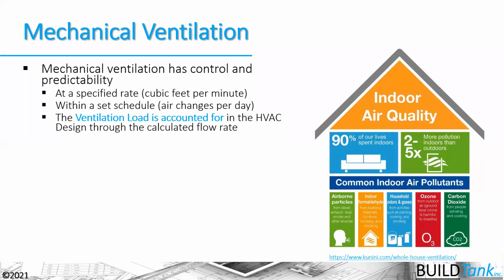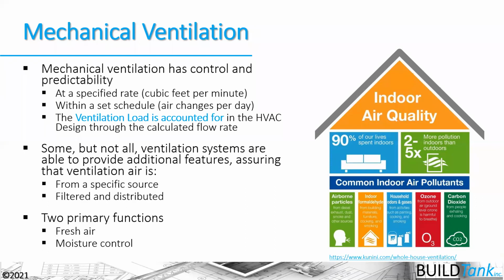Now, the other thing that is a little bit confusing to people is that ventilation can happen in a number of different ways. You can have exhaust and supply ventilation, or you can have balanced ventilation systems in your house. Exhaust and supply ventilation systems, although they use the same holes that air is moving through for air leakage and infiltration and exfiltration, do continue to put that air that's moving in and out of the house at a specific rate and a set schedule. So we know exactly how much air is moving in and out of the house. We just might not know exactly where it's moving through or what holes it's moving through. So it's really important to count mechanical ventilation and infiltration as two separate and distinct loads that are incorporated and designed for in that Manual J process.